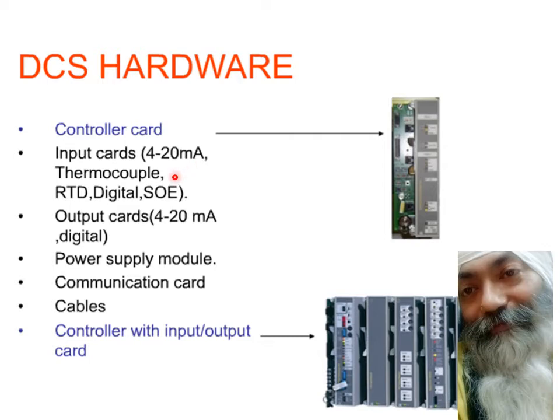Input cards can be directly interfaced with sensors like thermocouples or RTDs. Similarly, we have output cards which can be digital or analog, giving 4 to 20 milliampere. Along with that, any hardware includes a power supply module, a communication card for modules to communicate amongst themselves, and the required cables. All these control cards fit into racks — this is how DCS looks in general.